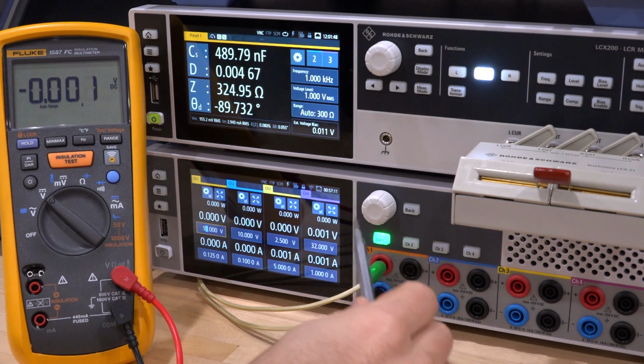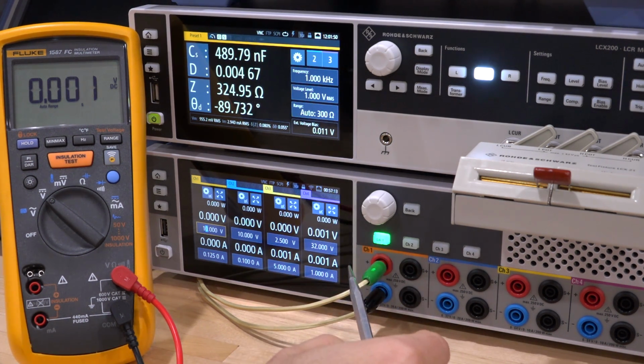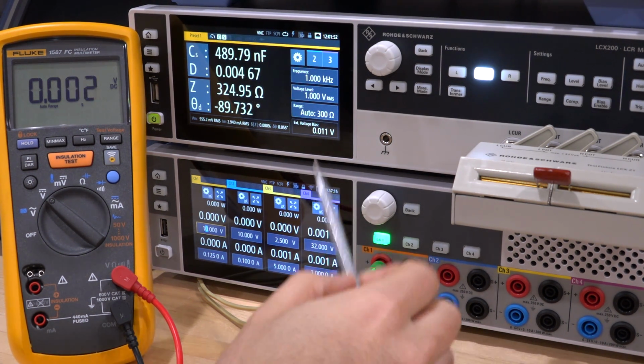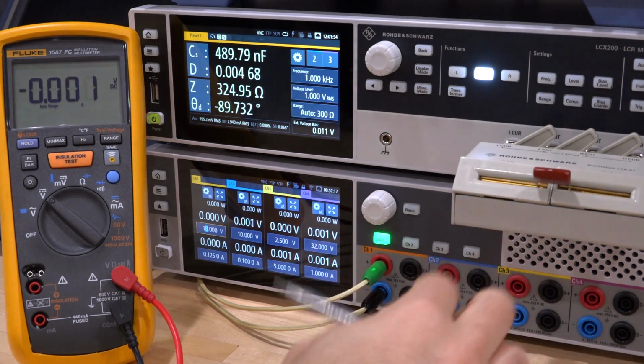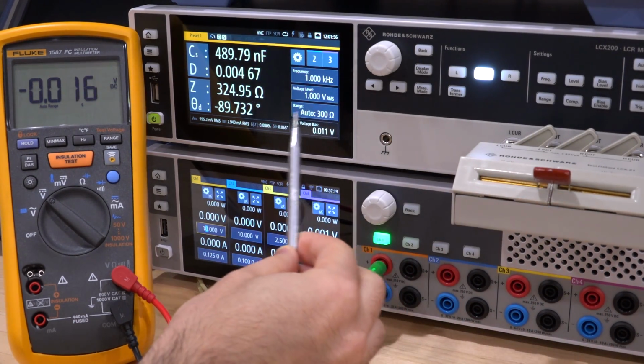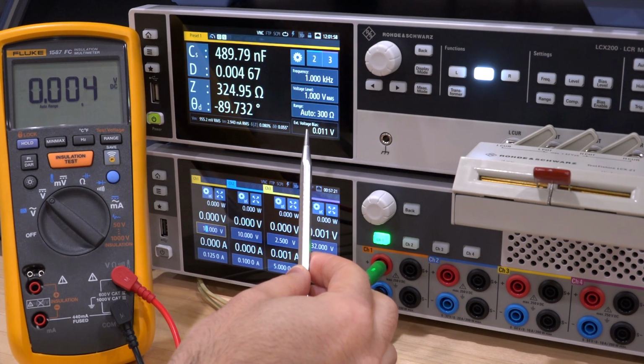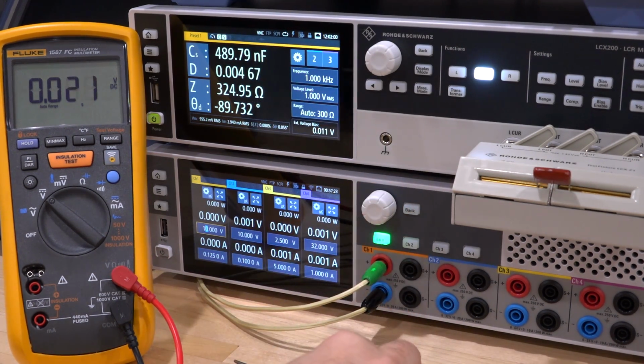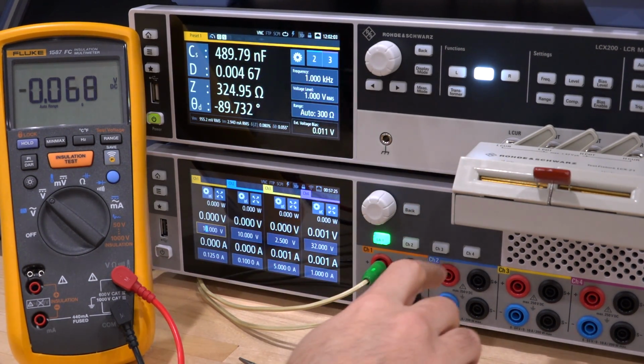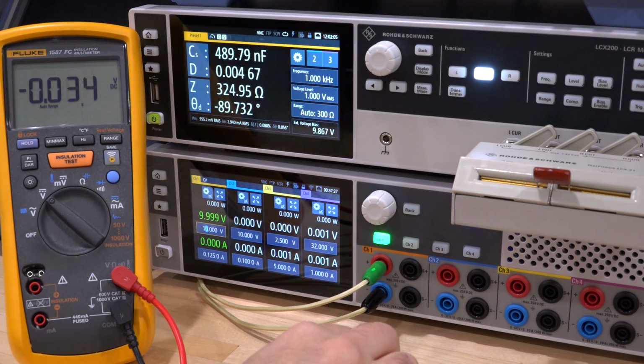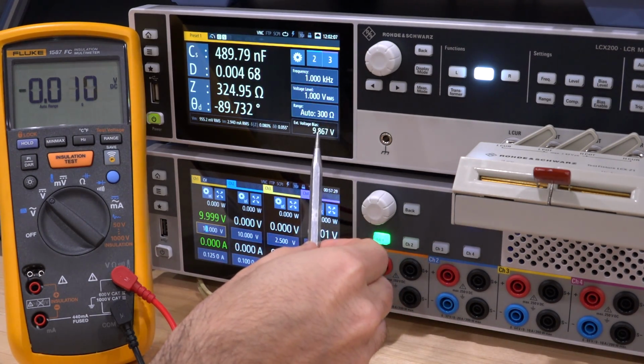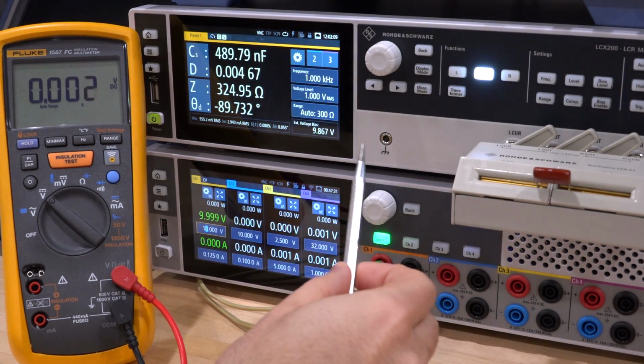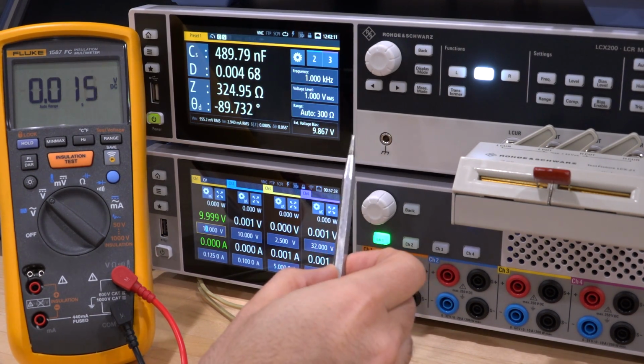I have connected the back of the unit to the power supply output here at the bottom. Right now the power supply is disabled and the bias is also disabled. So we do get this little external voltage display here, which is supposed to tell us what voltage would appear on the capacitor or whatever device that you have connected. So it's going to enable the power supply at the bottom. As soon as I do that, I do get the voltage readout over here, even though the bias is not enabled, which is nice, so you know what voltage is there to be applied to the device.